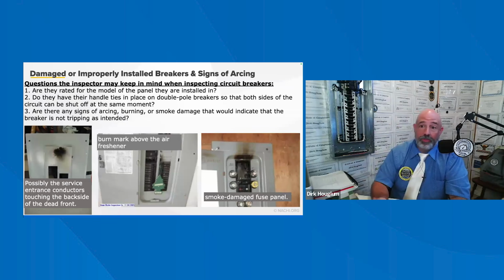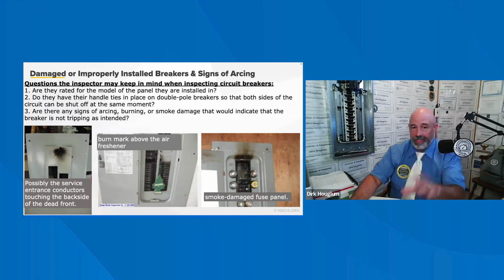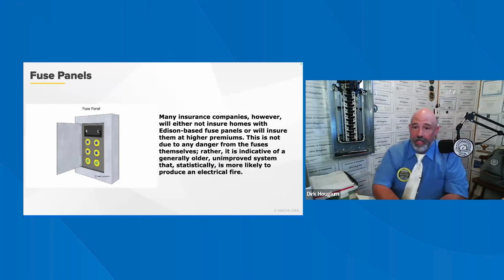As part of the initial inspection of the panel, the inspector should look closely for signs of arcing and things like that. I've seen where something blew out inside the electrical panel and was not pretty. So definitely keep an eye on stuff like that.